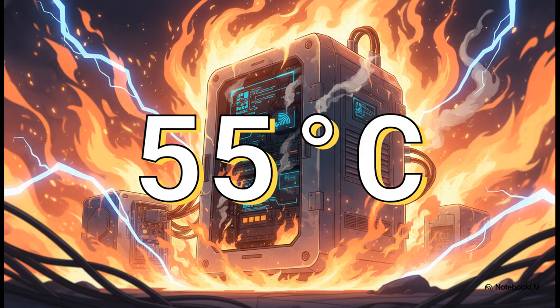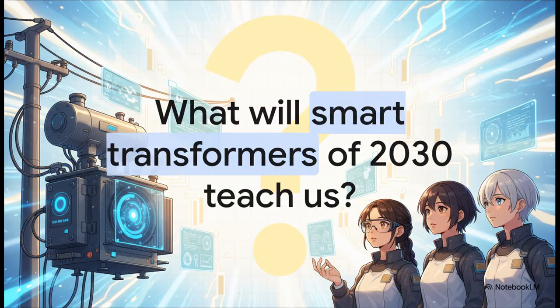Think about that for a second. You've got a sealed steel box baking in 55-degree heat while it's still accurately processing data, running cellular communications, and physically switching hundreds of amps of power, all without a single failure. It is seriously impressive engineering. It's just incredible to see how these engineering standards evolve. What started out as basic guidelines has morphed into a rigorous blueprint for a highly intelligent, self-preserving grid protector. As these asset performance management systems roll out, they're doing way more than just measuring current. They're extending the life of our infrastructure and actively preventing catastrophic blackouts.